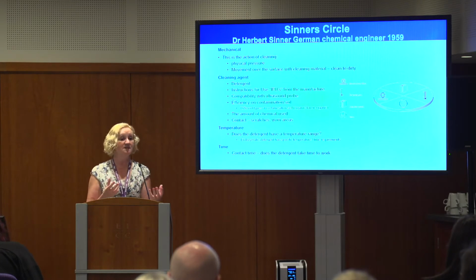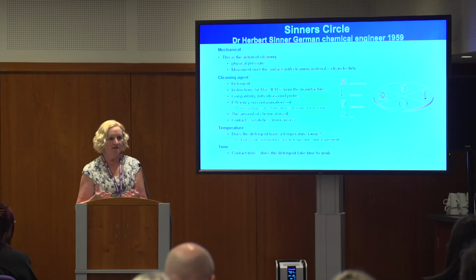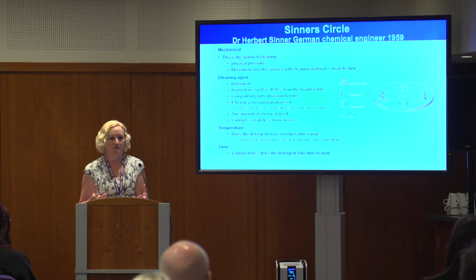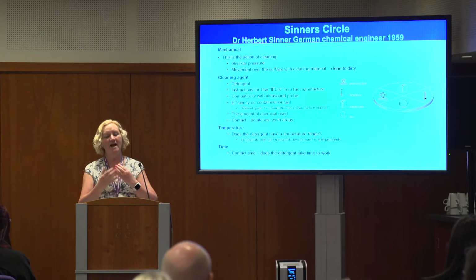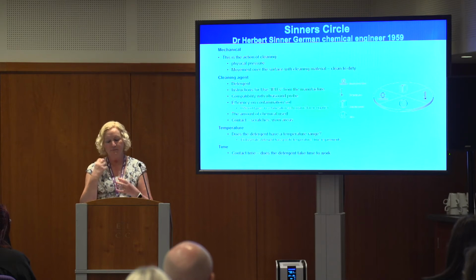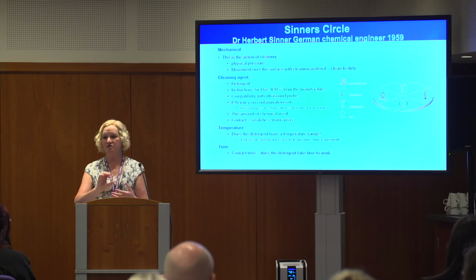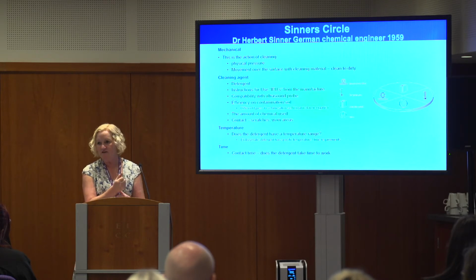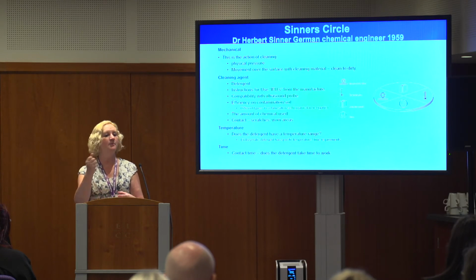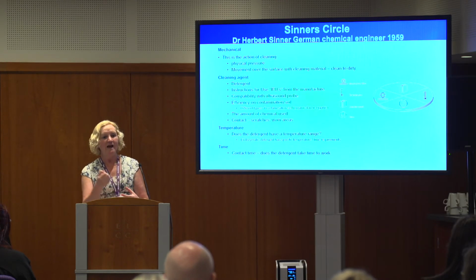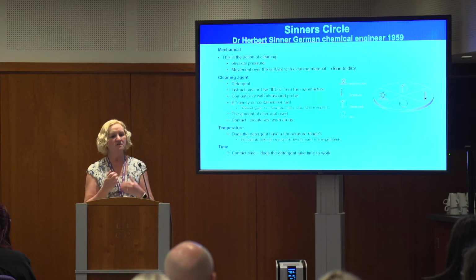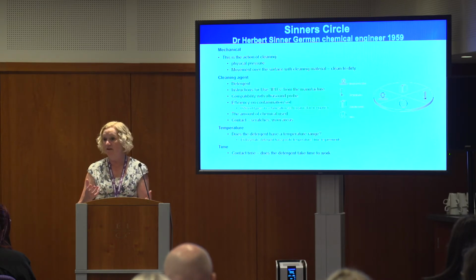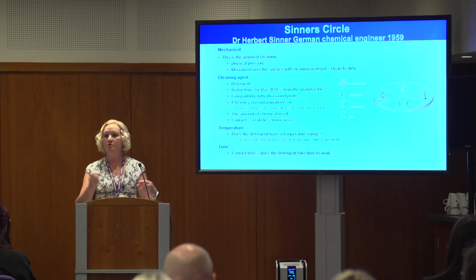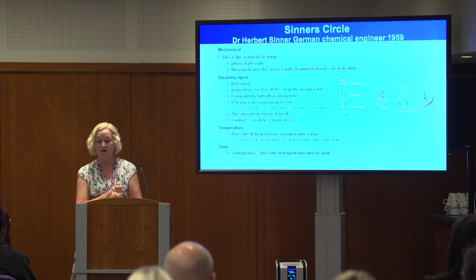You're looking at Sinner's Circle. Now this was developed in '59, donkey's years ago. But there are four aspects to Sinner's Circle. The mechanical action, so how you physically clean that probe, the pressure you put on it. So if you squeeze it really hard with your detergent wipe or whatever you're going to use, everybody will do it slightly differently. What's the contact time for the detergent wipe? Is it a minute? Is it 30 seconds? How do you do it? Does everybody know you go from clean to dirty, or are some people doing it the other way around?